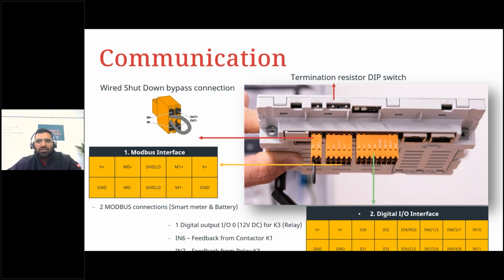Moving on to the brain of the machine, the data communication PCB. So on Fronius inverter, we are calling this data communication PCB a pilot. Here you have a picture of a pilot. As you can see, it has a wired shutdown terminal, a Modbus interface, and a digital I/O. The Modbus interface has 2 Modbus connections, as mentioned again, M0 and M1 terminal. So it makes it easier for you to connect a meter and a battery.